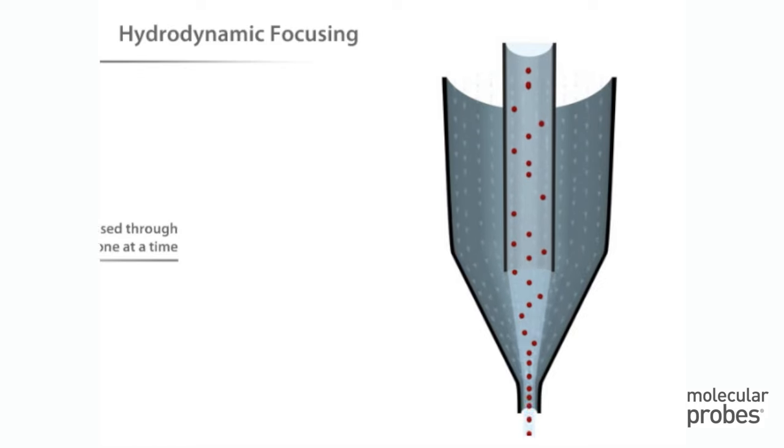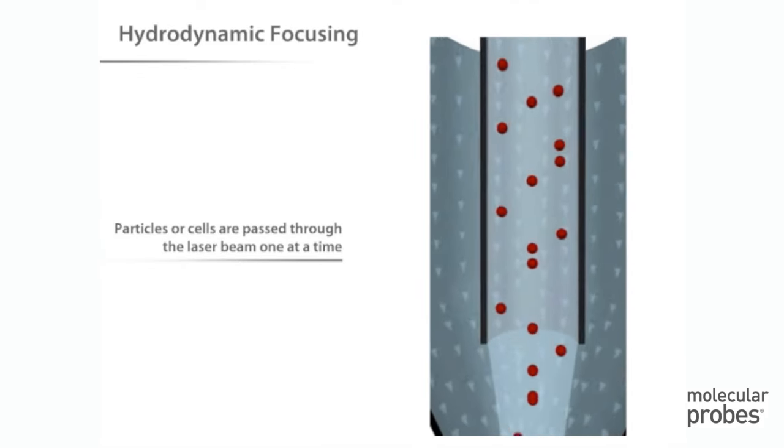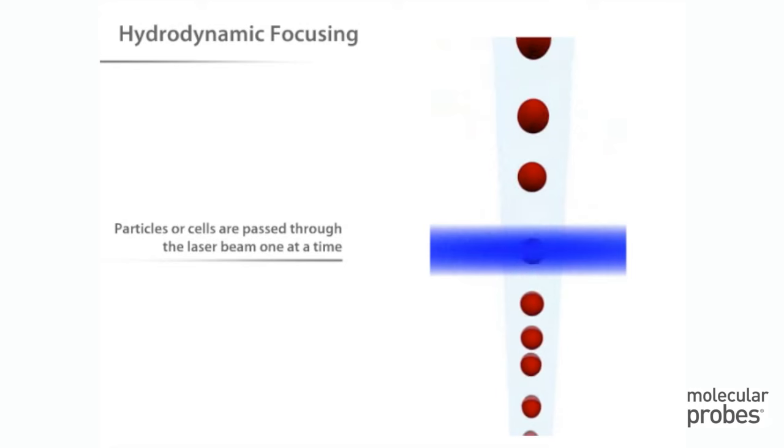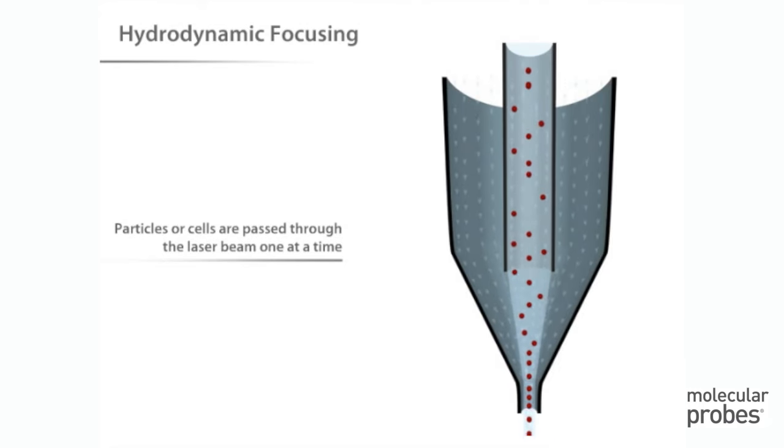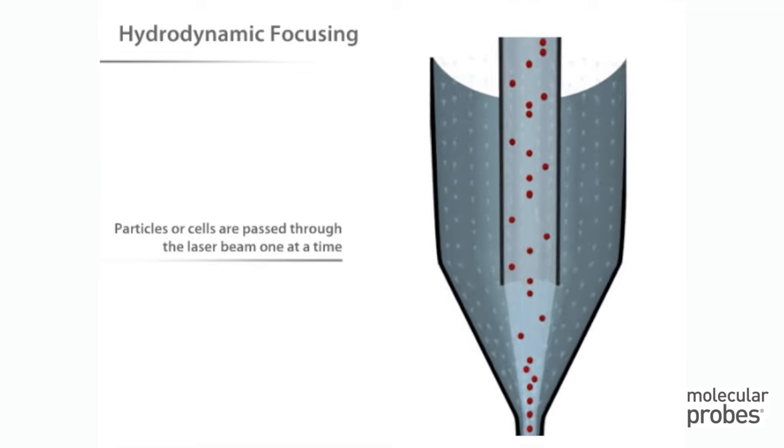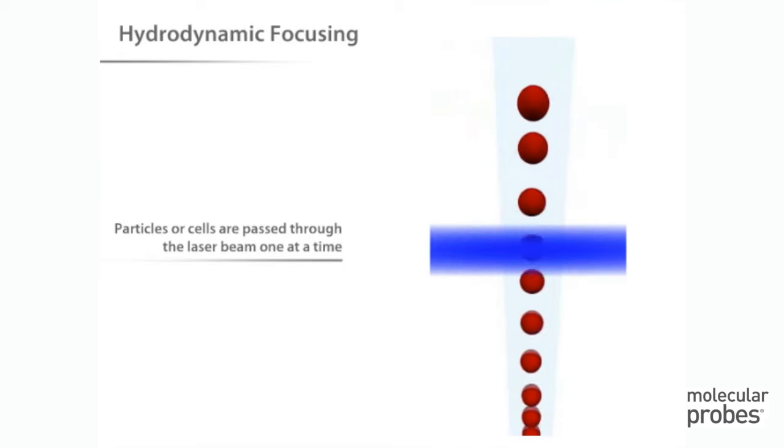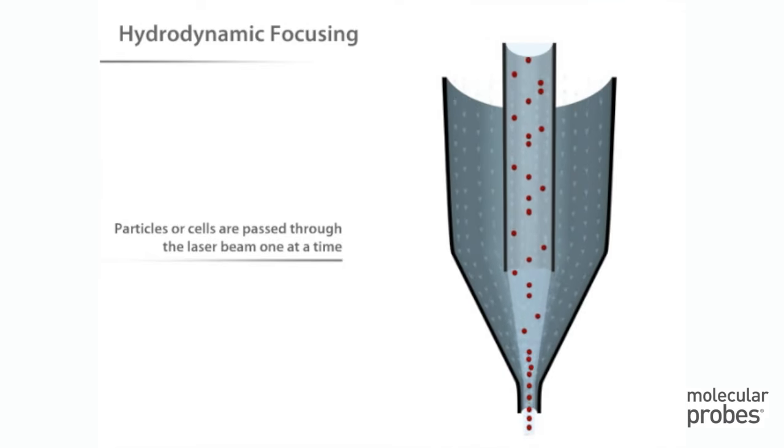For accurate data collection, it is important that particles or cells are passed through the laser beam one at a time. Most flow cytometers accomplish this by injecting the sample stream containing the cells into a flowing stream of sheath fluid or saline solution. As you can see, the sample stream becomes compressed to roughly one cell in diameter. This is called hydrodynamic focusing.